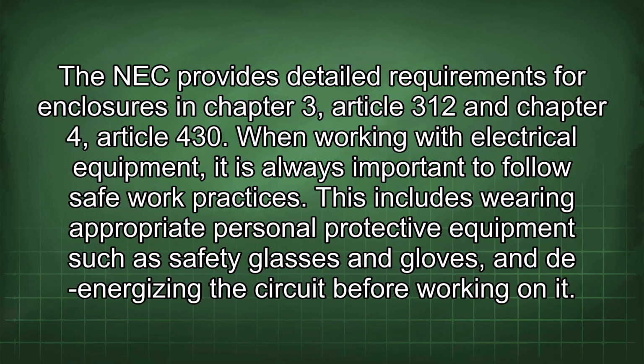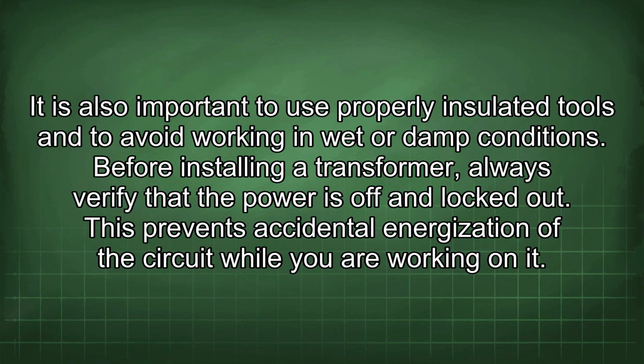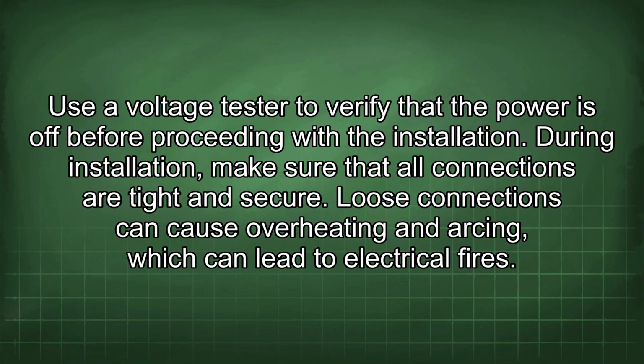When working with electrical equipment, it is always important to follow safe work practices. This includes wearing appropriate personal protective equipment such as safety glasses and gloves, and de-energizing the circuit before working on it. It is also important to use properly insulated tools and to avoid working in wet or damp conditions. Before installing a transformer, always verify that the power is off and locked out. This prevents accidental energization of the circuit while you are working on it. Use a voltage tester to verify that the power is off before proceeding with the installation.